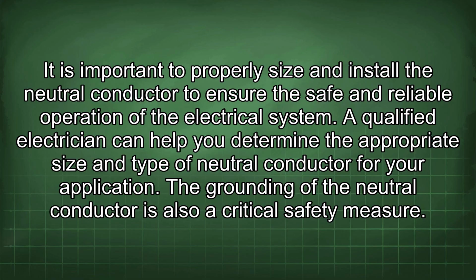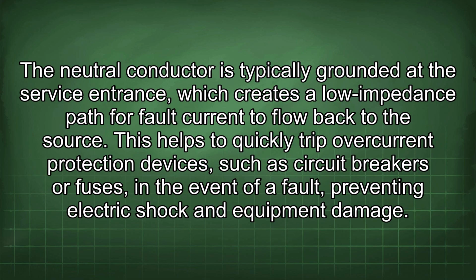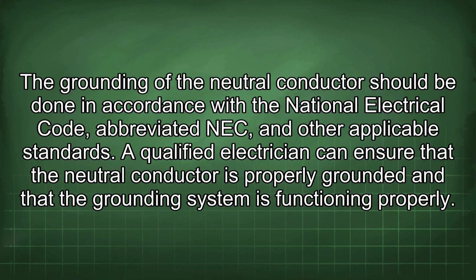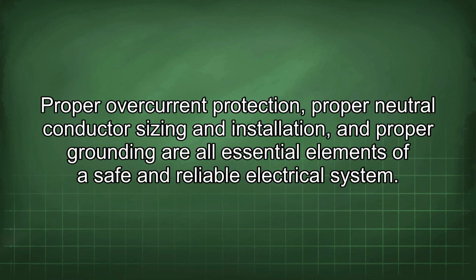The grounding of the neutral conductor is also a critical safety measure. The neutral conductor is typically grounded at the service entrance, which creates a low impedance path for fault current to flow back to the source. This helps to quickly trip overcurrent protection devices, such as circuit breakers or fuses, in the event of a fault, preventing electric shock and equipment damage. The grounding of the neutral conductor should be done in accordance with the National Electrical Code, abbreviated NEC, and other applicable standards. A qualified electrician can ensure that the neutral conductor is properly grounded and that the grounding system is functioning properly. Proper overcurrent protection, proper neutral conductor sizing and installation, and proper grounding are all essential elements of a safe and reliable electrical system.